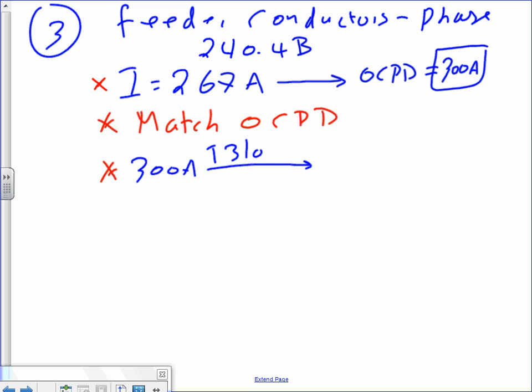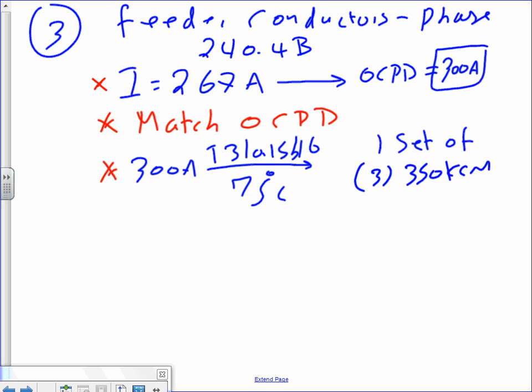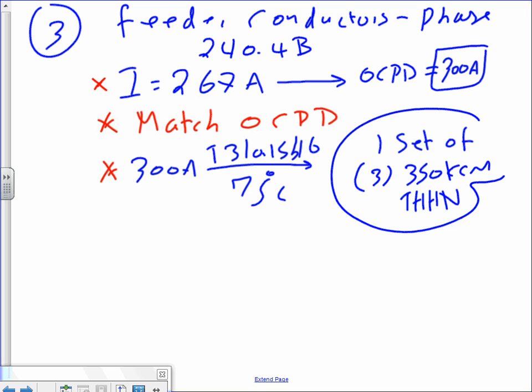Take it to table 310.15(B)(16), under which column? The 75-degree column. And that will get you what conductor size again? That will get you one set of 3 conductors, 350 kcmil, THHN. Can anybody tell me why THHN? We're pulling in EMT conduit like this, indoor, so THHN. It's a feeder. Where do you put the feeders typically? Indoor. They're not coming from outside. Okay. Where's my neutral? That's next. My neutrals, these are 3 phases.